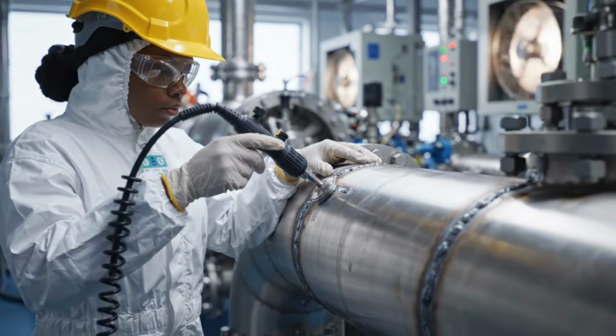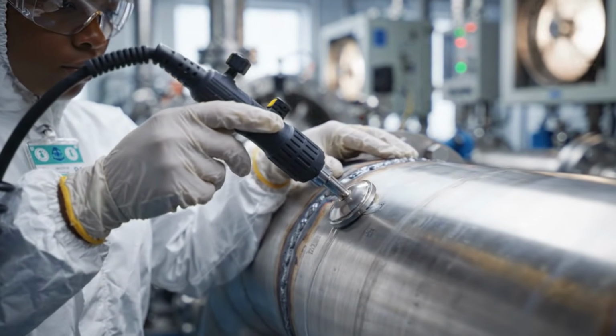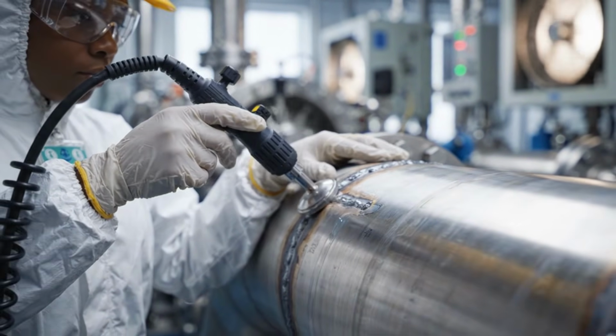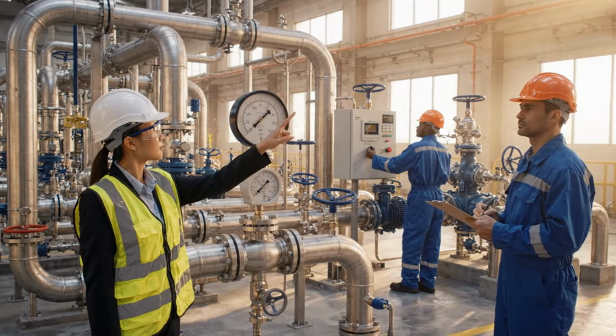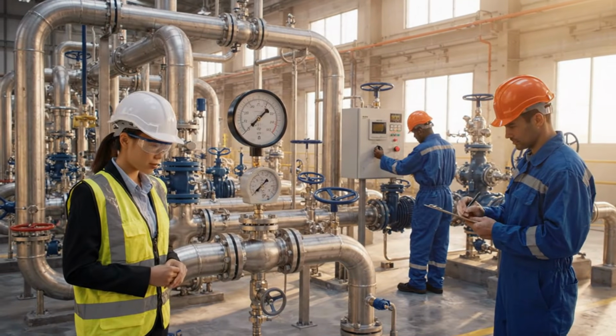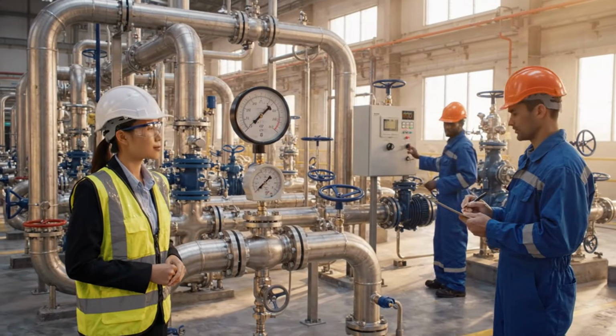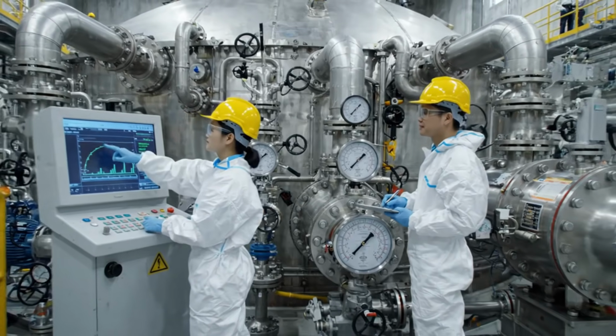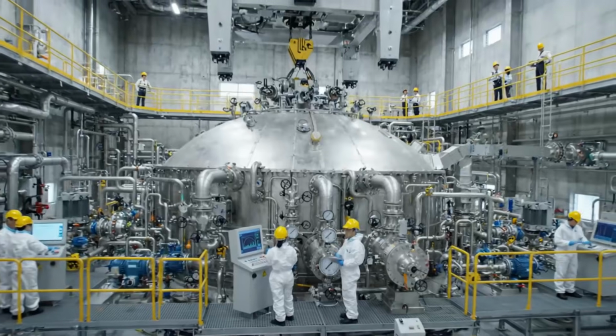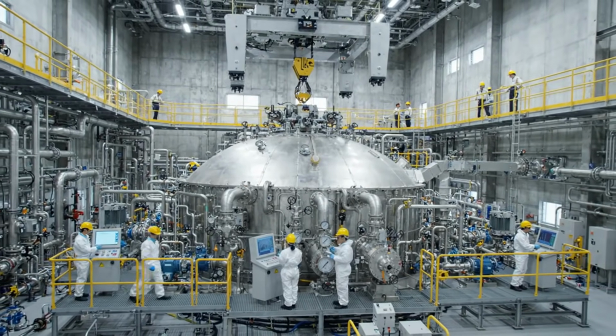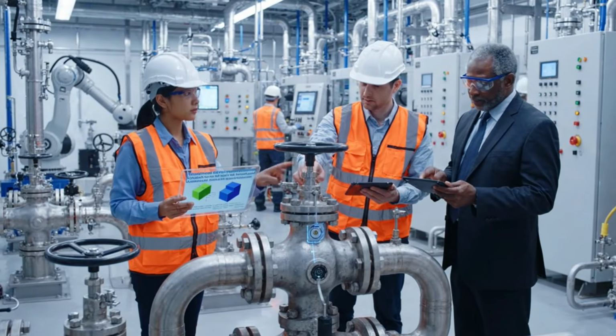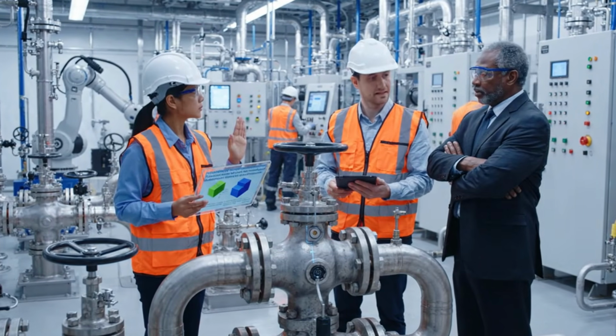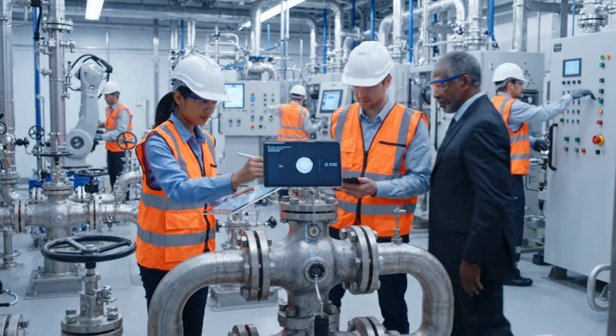The repaired weld must undergo the full inspection process again and cannot be accepted merely because it was repaired. The system is then pressure tested to prove its boundary can withstand pre-operational test conditions. Containment is also leak tested, searching for tiny leakage paths before fuel enters the plant. Records are updated from cause through repair, turning one small deviation into a lesson for the entire project.